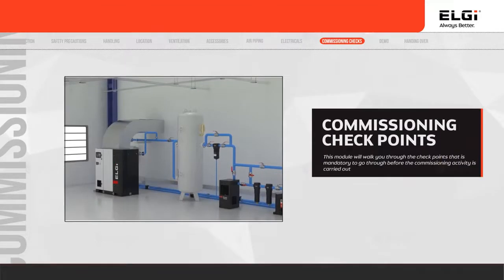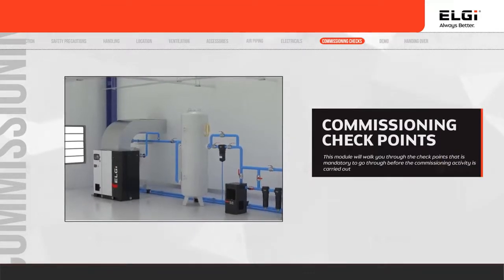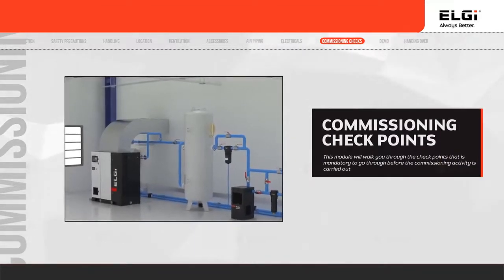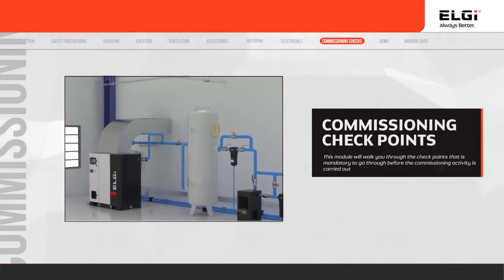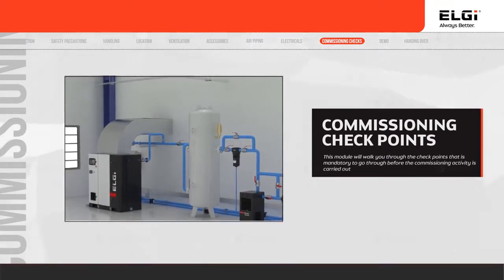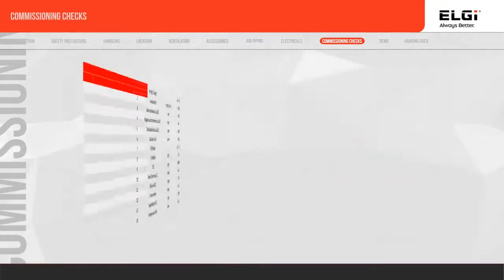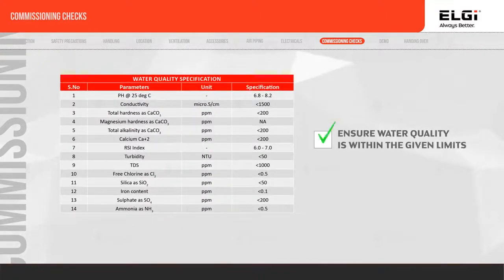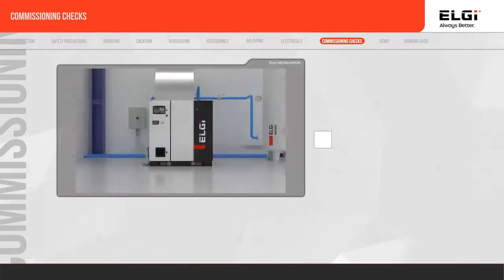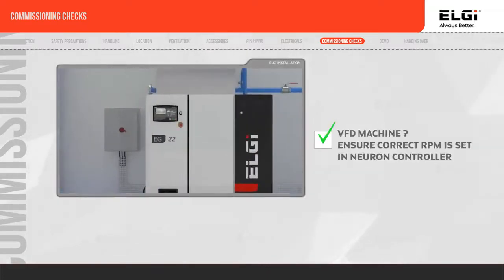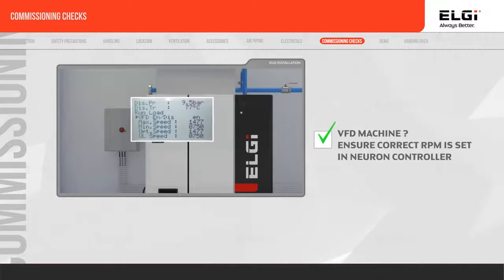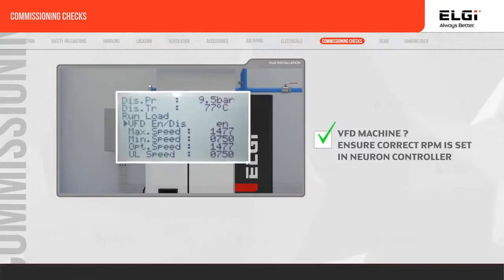Before commissioning the system, it is mandatory to carry out a few important checks. Failure to do so might result in damage to the compressor and delay in handover. If the compressor you are installing is a water-cooled machine, ask for the feed water analysis report, and ensure the parameters are within the given limits. If this is a VFD machine, ensure the RPM setting is correct in the neuron controller for operating pressure.